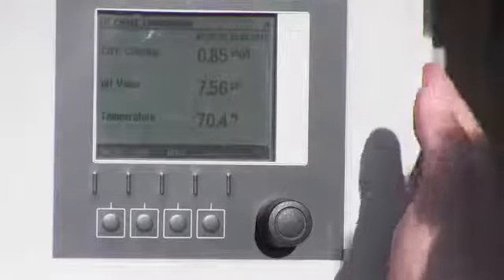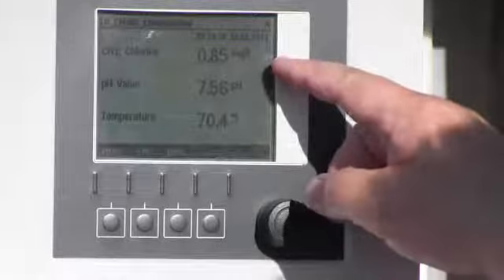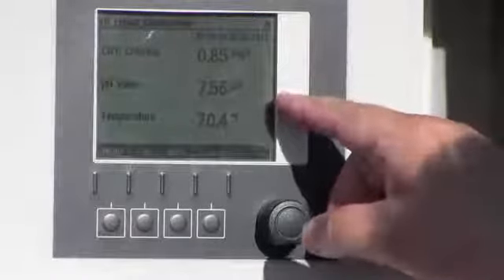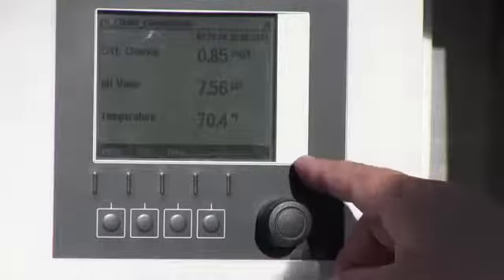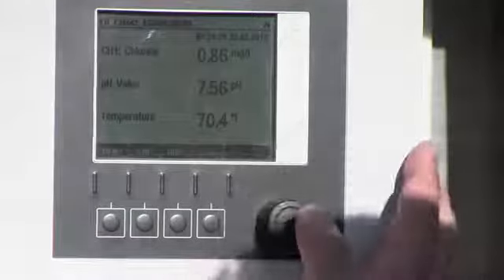So this is the normal screen you're going to see when you walk up to the analyzer. Top line, residual chlorine. Middle line, pH value. Bottom line, temperature. First thing to note is that if you haven't been around the transmitter for more than about a minute pushing the buttons, it will go into an energy save mode and turn off the backlight. Any button you touch for the first time will cause the backlight to come on, but no action is taken. So it's easy to think that nothing happened when you push the button.